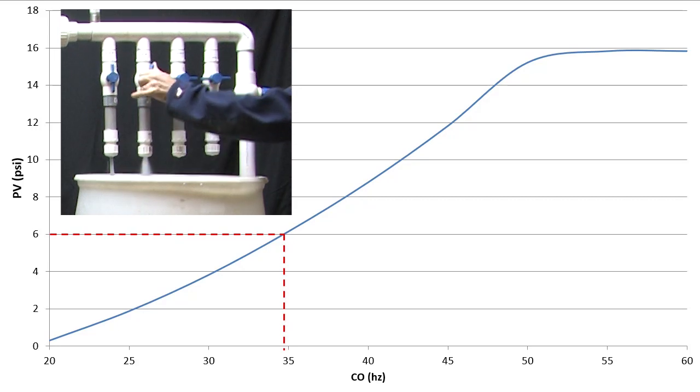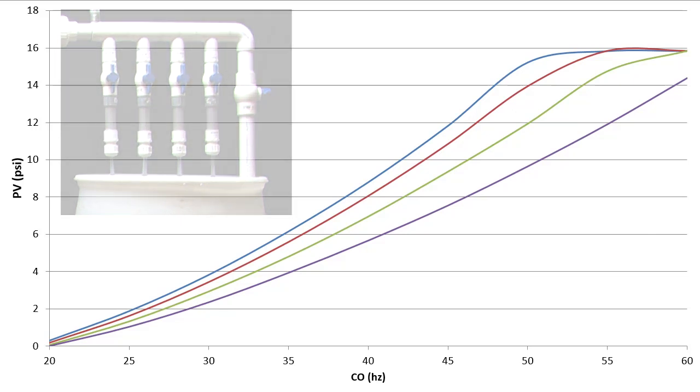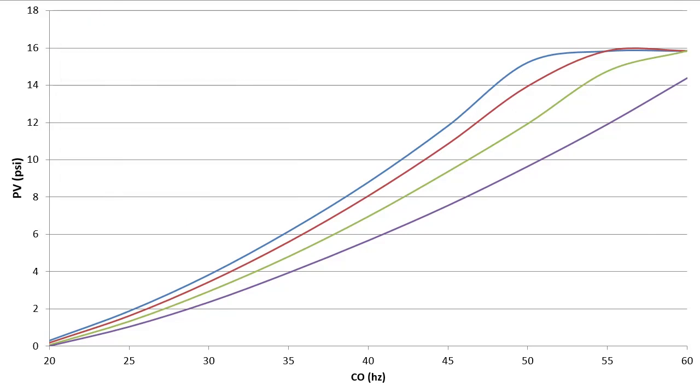I repeated that exact procedure with 2 valves open, 3 valves open and 4 valves open. Looks like with 4 valves open, our motor needs to be at a little over 40 Hz to get the 6 psi we need.